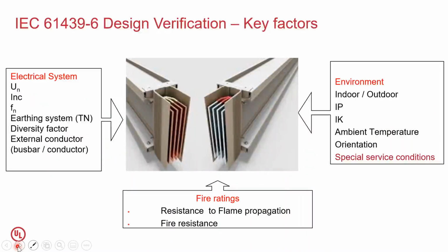Now, for design verification, you can broadly classify. One is the electrical system, which is the key. When I talk about the electrical system, you need to know the rated voltage under which these busways are going to be used. You need to know the rated current that these busways have to carry. You need to know the frequency, whether it is 50 hertz or 60 hertz. You need to know the earthing system, whether it is TN or TT. Based on that, you will decide to provide your earth bar accordingly.